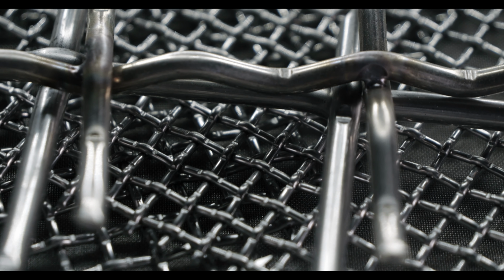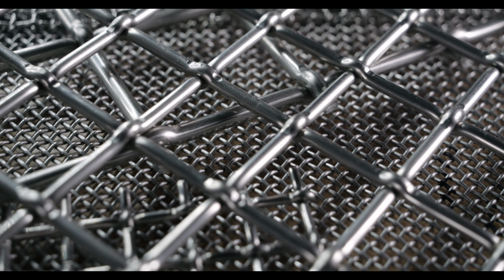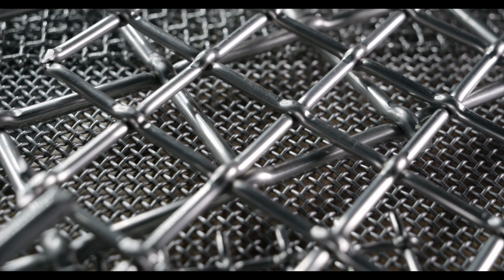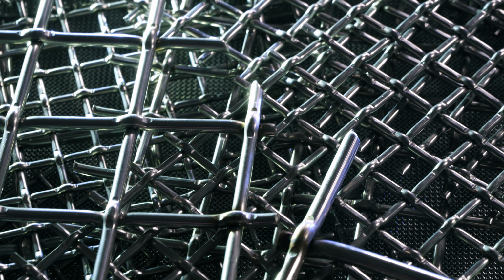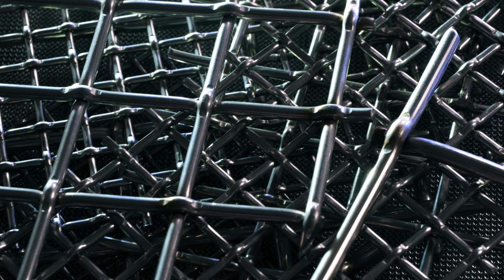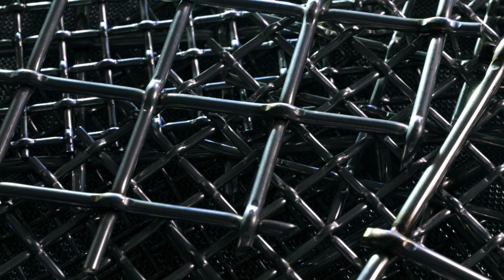Material selection is often a trade-off between upfront cost and life cycle performance. 316 may appear to be economical initially, but its susceptibility to pitting and crevice corrosion leads to frequent maintenance and early replacement. 904L offers a moderate upgrade with better corrosion resistance and lower nickel content than super austenitic grades. 254 SMO, while usually more expensive, delivers superior performance in aggressive environments, reducing downtime and extending service life.